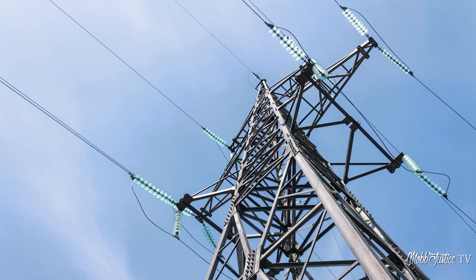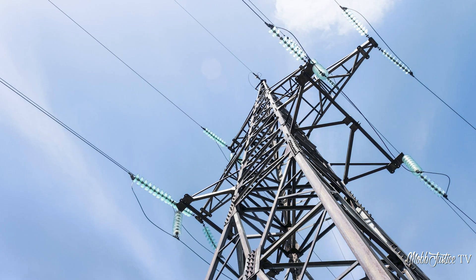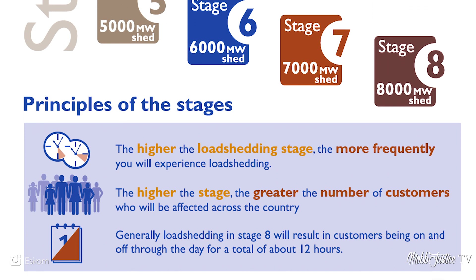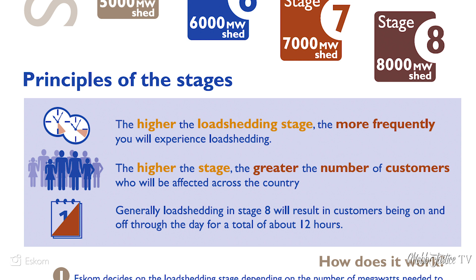This is the heart of the issue around why the network sucks during load shedding. It helps to remember the hours of outages at various stages. Some operators have backup power that lasts four hours, some up to six hours. For stages one to four of load shedding, this has normally been okay. But beyond that — where South Africa is now, predominantly stage five and six — power can be out for up to nine to ten hours a day.